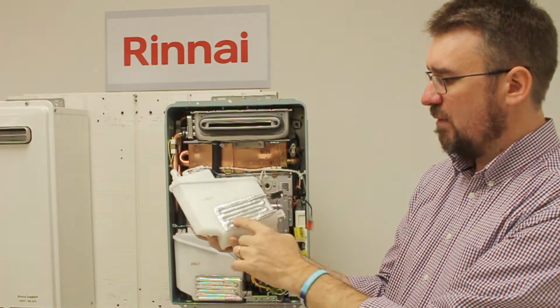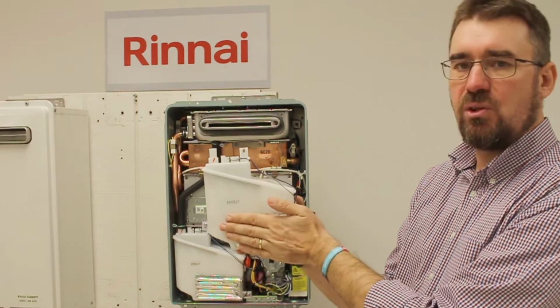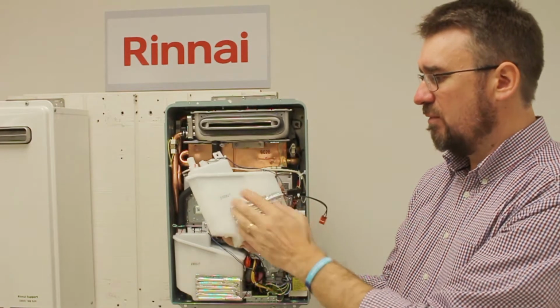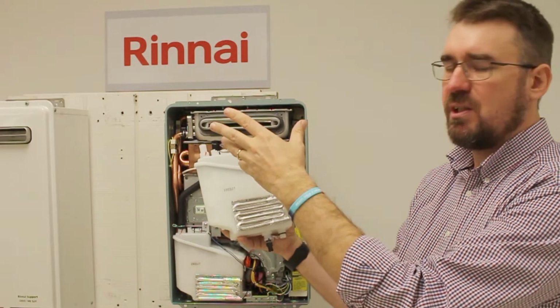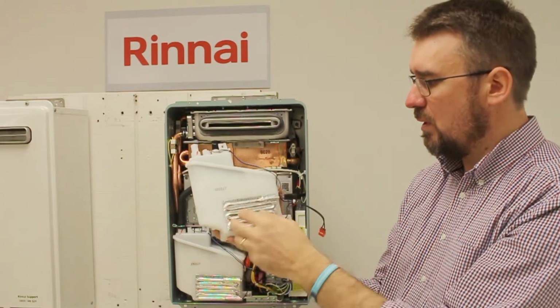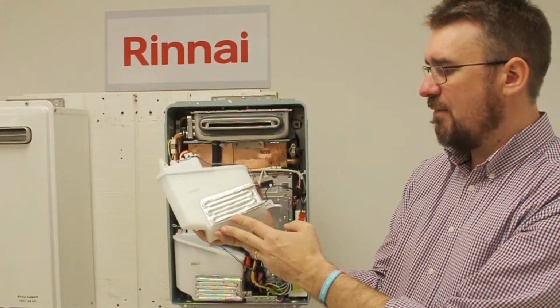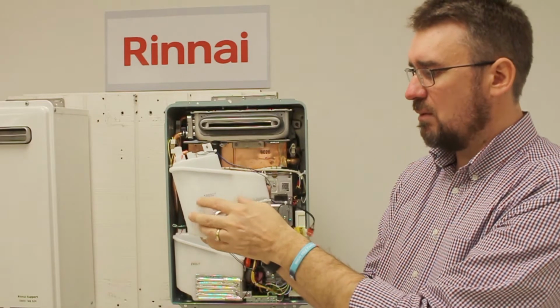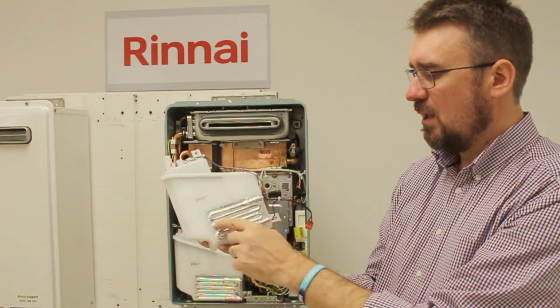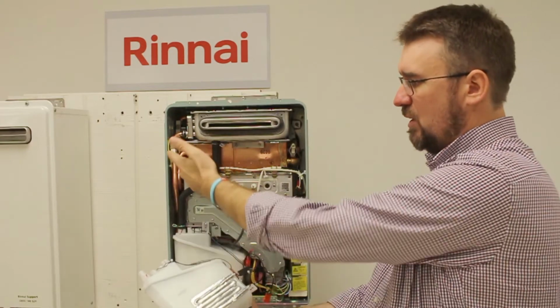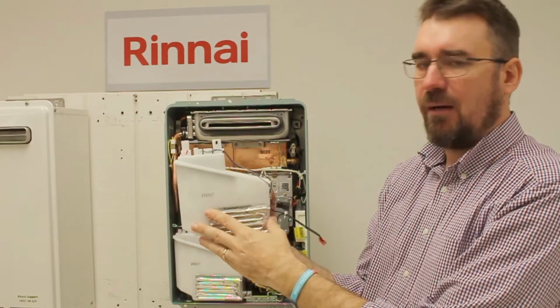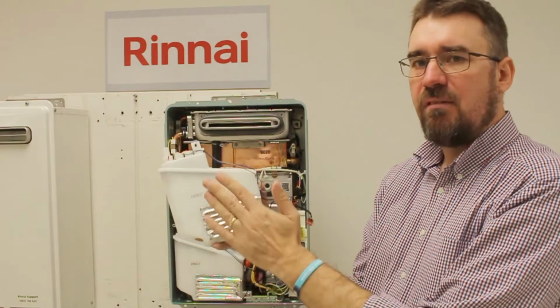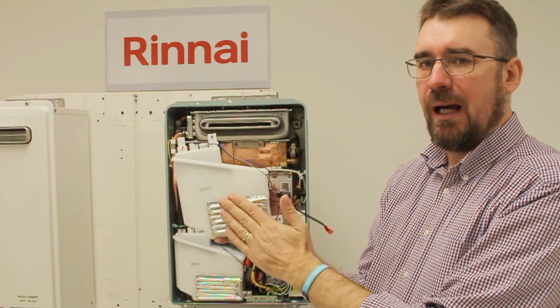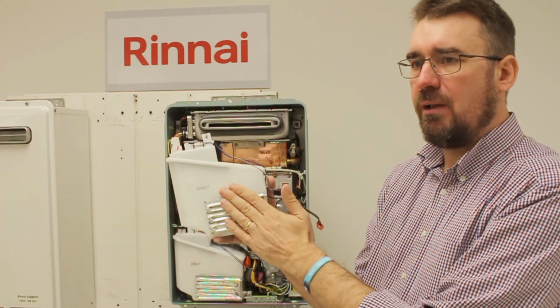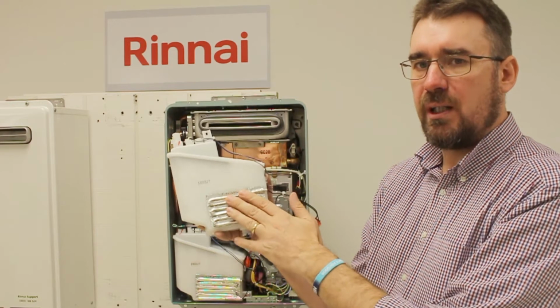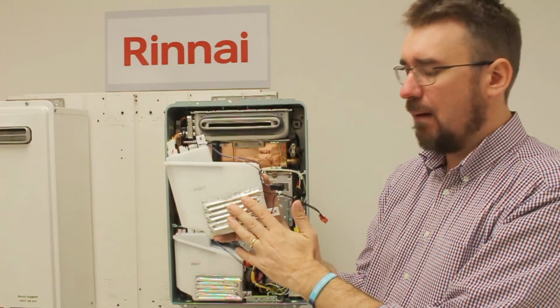This thing on the front in silver is just a little element keeping it nice and warm, frost protection for the condensate pack. If the unit gets into sub-zero temperatures, winter time, high up or down in the South Island, this can start to get cold and want to freeze. This element switches on as part of the frost protection we've got on the unit, and just keeps the pack from freezing. For that to happen, the unit's got to be connected to power all the time. So no power on the unit, cold weather equals cold unit equals frost problem. Make sure the power is on.